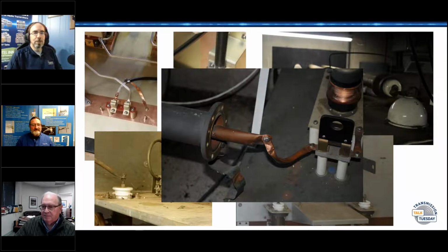And the same is true for guy wire insulators. When Keith was talking about hearing them start to snap - once a guy wire insulator arcs, it develops a carbon track, and after a couple of times, it's no longer an insulator, it's a conductor waiting for a chance to happen.